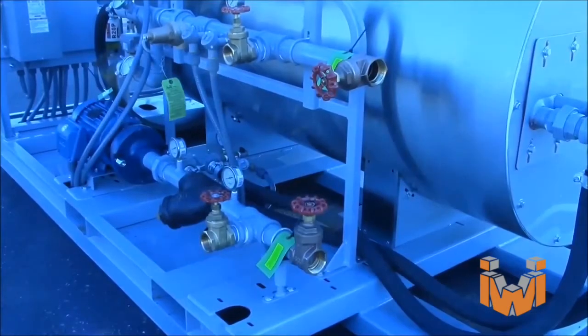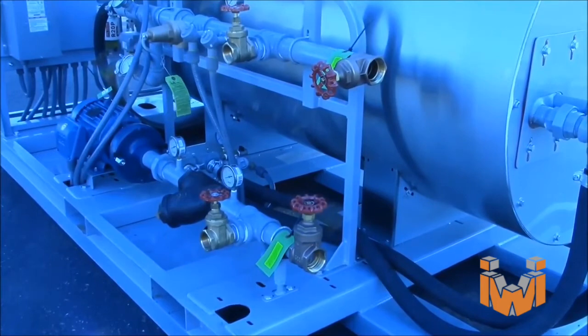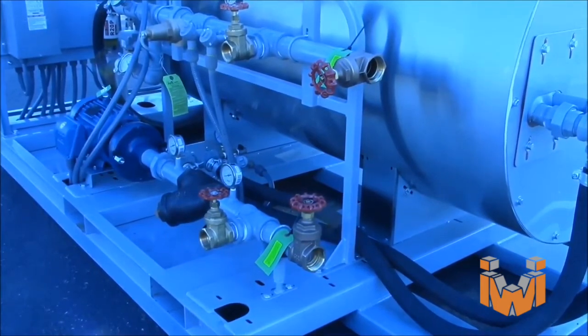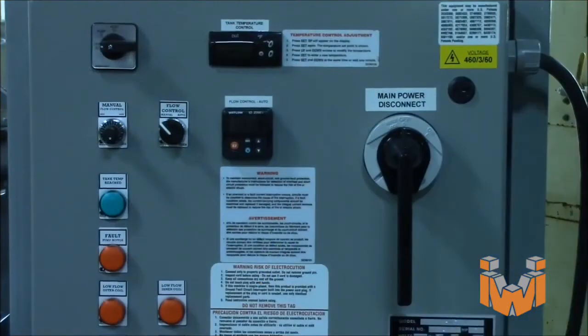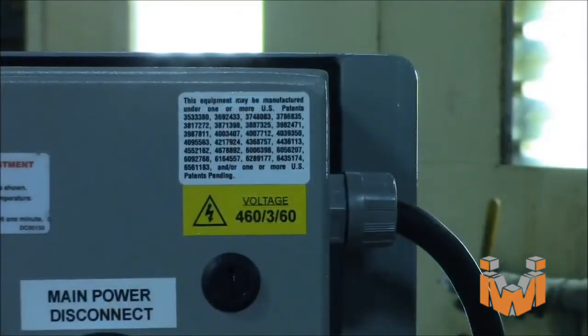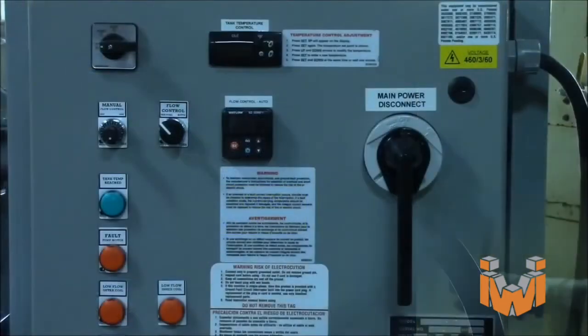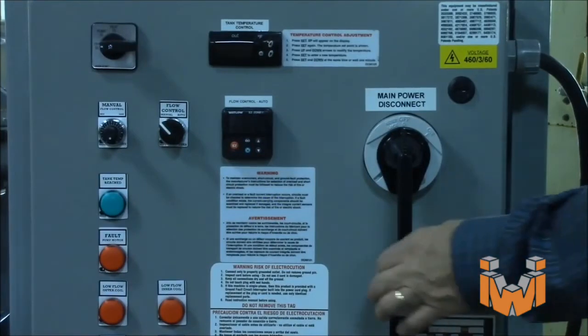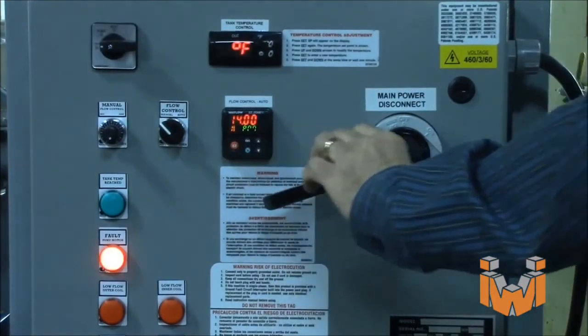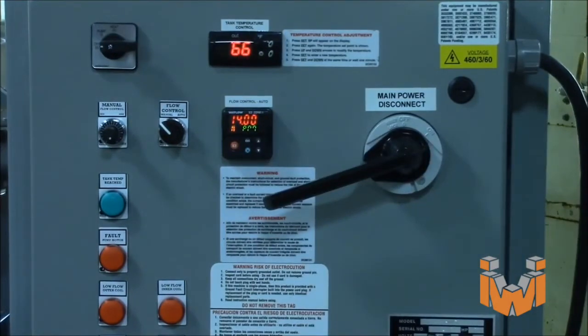The water connections are both located on the exhaust end of the skid. The lower connection is for inlet water, and the upper connection is the outlet. Use piping or approved hoses to connect the inlet and outlet to your water tank. Each HM 1.7 will have a label in the upper right corner of the control panel that designates its required electrical supply. After a qualified electrician has wired power to the machine, you may turn the disconnect switch to the on position. The control panel instruments will turn on.